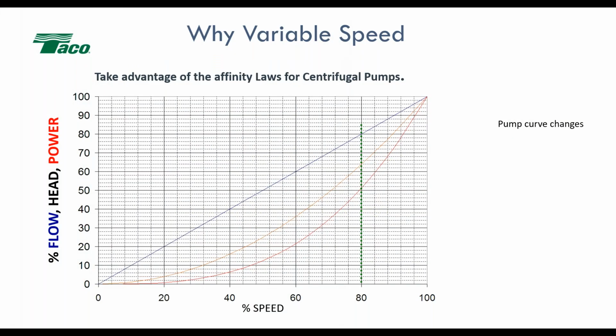So to look at this more graphically, if we look at this at 80% speed, we have 80% flow. The left-hand axis, the vertical axis, is in percentage, so it's 0 to 100%. And it's also 0 to 100% across the horizontal axis for speed. So if we look at the very top point in the far upper right corner, that is our 100% speed, 100% flow, 100% power. Now, as we start to slow down and drop the speed down to 80%, that's represented by the green line, we see that the flow is now 80%. As we continue down, what we see is that the head is 64%.